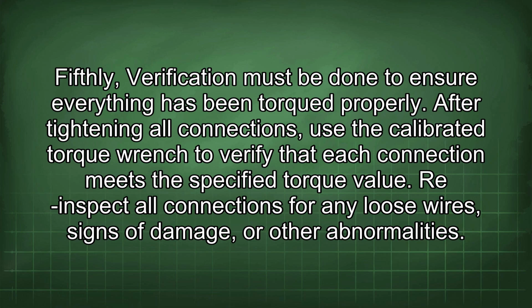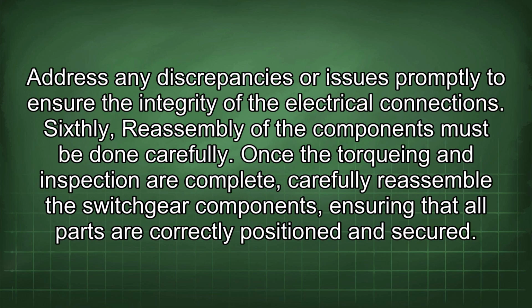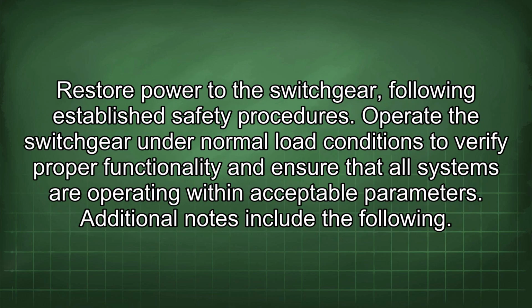After tightening all connections, use the calibrated torque wrench to verify that each connection meets the specified torque value. Re-inspect all connections for any loose wires, signs of damage, or other abnormalities. Address any discrepancies or issues promptly to ensure the integrity of the electrical connections. Sixthly, reassembly of the components must be done carefully. Once the torquing and inspection are complete, carefully reassemble the switchgear components, ensuring that all parts are correctly positioned and secured. Restore power to the switchgear following established safety procedures.